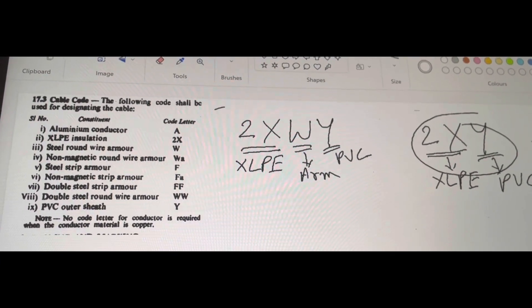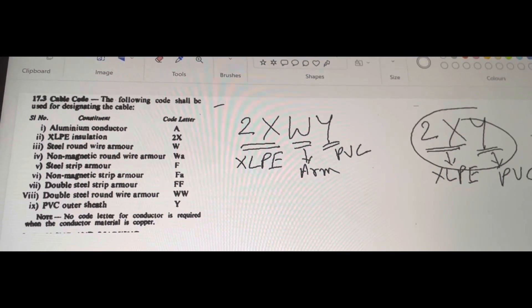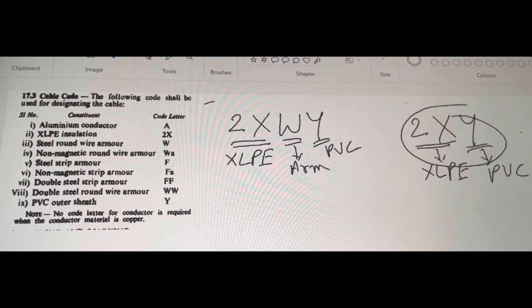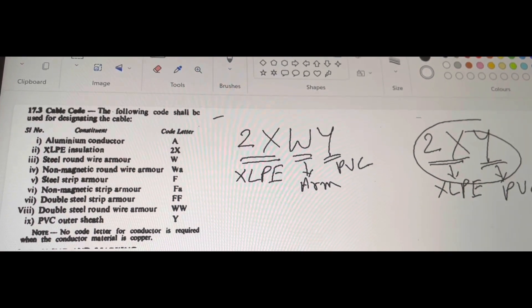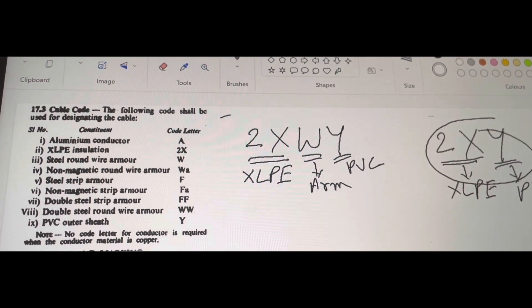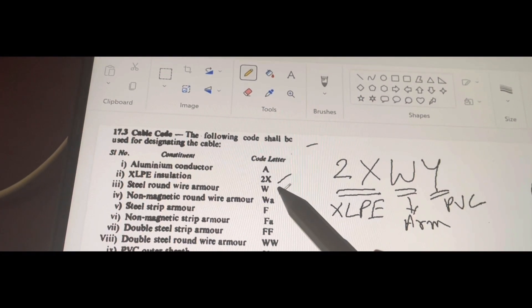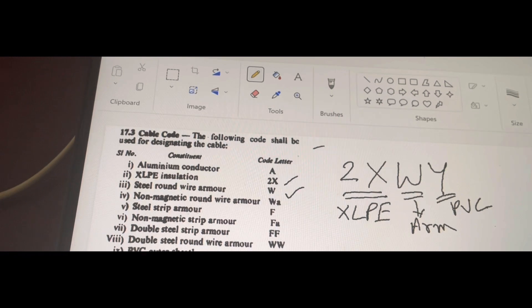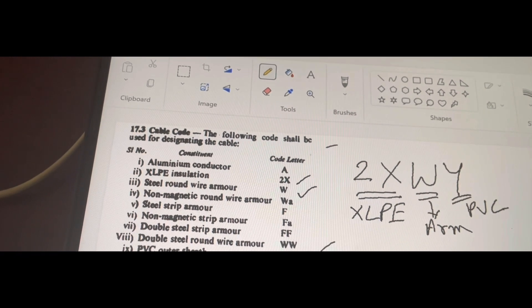And these cable codes are given in Indian standard 7098 part 1. And on the screen you can observe there is a table which indicates the meaning of these letters. And 2x this is nothing but XLPE insulation and w indicates steel round wire armor and y indicates PVC outer sheath.